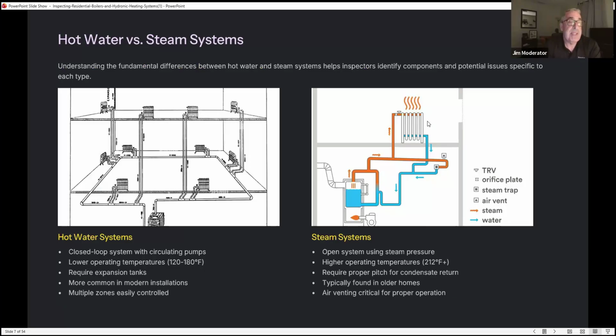Hot water versus steam systems. Understanding the fundamental differences between hot water and steam systems helps inspectors identify components and potentially issues specific to each type. So hot water systems, well, we have a closed loop system with circulating pumps, lower operating temperatures between 120 and 180 degrees. They require expansion tanks. They're more common in modern installations, and multiple zones are easily controlled.